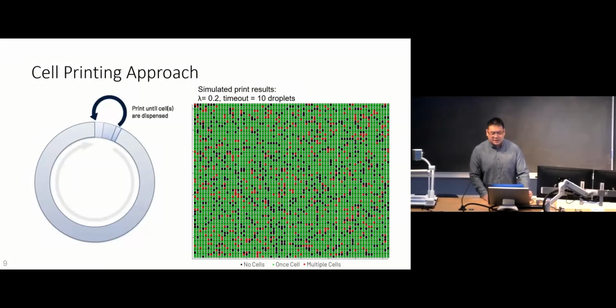dispensing. The instrument positions the nozzle over the target well and continues to eject droplets until a cell dispensing event has occurred. This can be from dispensing a single cell or multiple cells. To meter the volume of droplets dispensed into each well, a timeout condition can be added where if a number of consecutive empty droplets are dispensed, the well will be skipped and marked as containing no cells. Simulated results shown on the right of this print algorithm show that single cell rates beyond the Poisson distribution can be achieved while minimizing machine movement time, allowing for high throughput. As the locations of the single cells are known within the chip, those wells can then be selected for further processing.